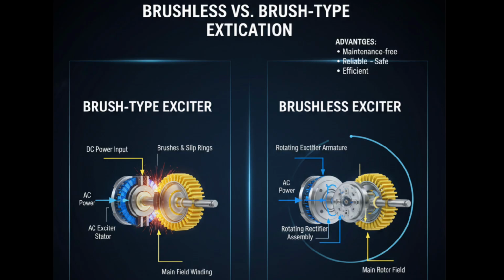AC generated by a small exciter mounted on the rotor is converted to DC by a rotating rectifier assembly and fed to the main rotor field. This system is cleaner, safer, and requires very little maintenance. The graphics also highlight how energy flows smoothly from the exciter to the rotor, without friction or sparking.